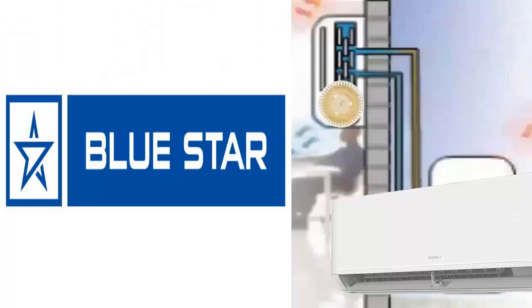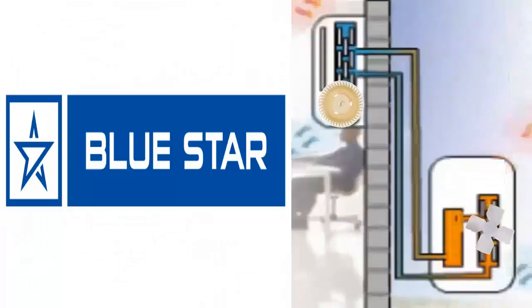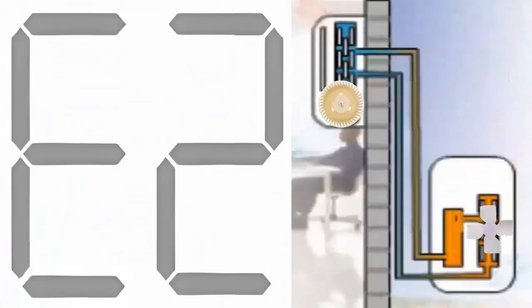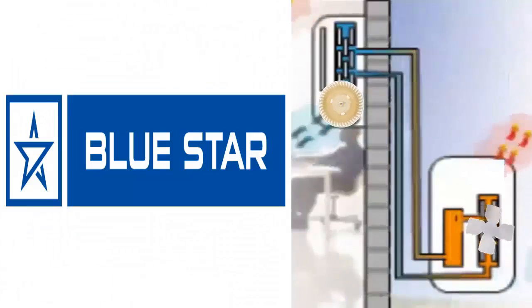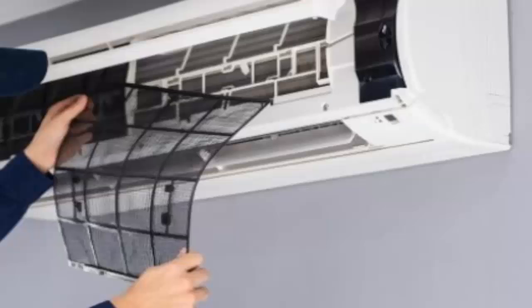It is important to mention that in some models, when the indoor unit coil freezes while the air conditioner is operating in cooling mode, code E2 may appear, indicating protection against indoor unit coil freezing. In this case, always remember to check the correct rotation of the indoor unit fan and the cleanliness of the air filters to ensure good airflow in this area.